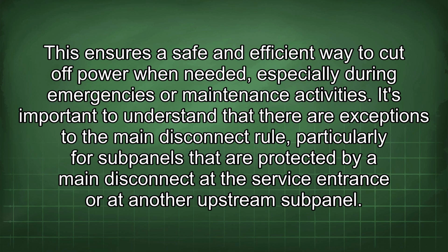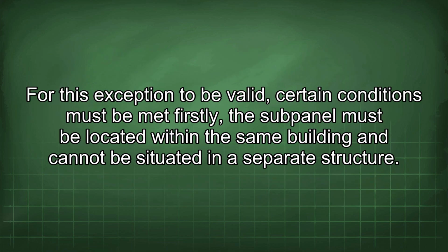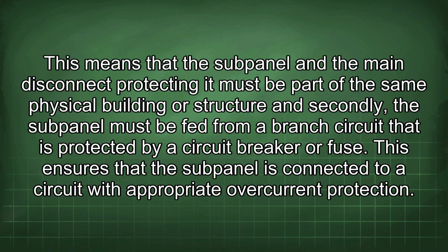It's important to understand that there are exceptions to the main disconnect rule, particularly for subpanels that are protected by a main disconnect at the service entrance or at another upstream subpanel. For this exception to be valid, certain conditions must be met. Firstly, the subpanel must be located within the same building and cannot be situated in a separate structure. This means that the subpanel and the main disconnect protecting it must be part of the same physical building or structure.